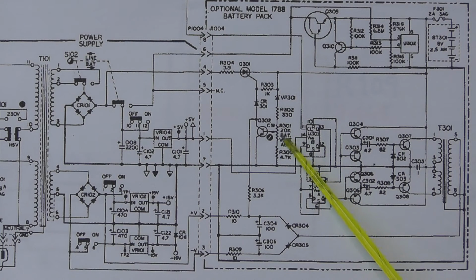This particular resistor here, a preset resistor, is adjusted at the factory at manufacture, and normally it's not needed to be adjusted thereafter. It's set to ensure that when the battery reaches that nominal level of 9.8 volts maximum, this transistor turns on, removes the bias from the gate of the SCR, switches the SCR off, and removes the charging current to the batteries. As the batteries start to discharge, the voltage drops. As soon as the voltage drops, this transistor switches off and the biasing current for the gate of the SCR is restored, switching back on the charging current.